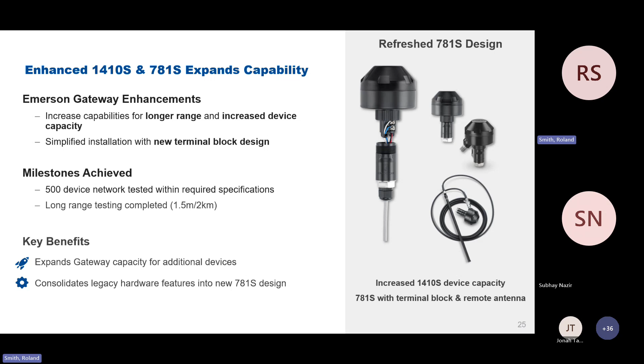The 1410S2, as I mentioned, is a field mount unit using the same 781S antenna. New to the portfolio, with these long cable runs, we now have the capability of running a home run of the 3084A cable, a straight run without any J-box in the field. The first antenna design had an integral 30 feet of cabling, so any further than that back to the gateway forced us to use a J-box. This enables a full run of Belden 3084A cable out to the gateway location, field connected, as you see on the terminal there.